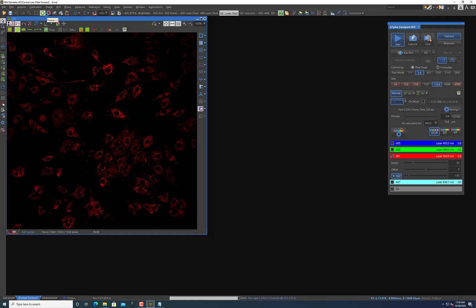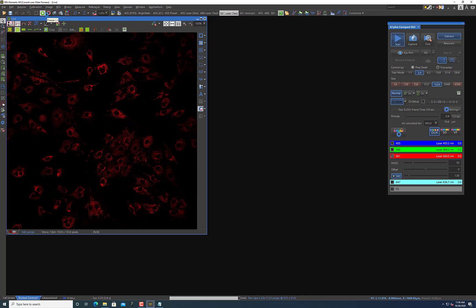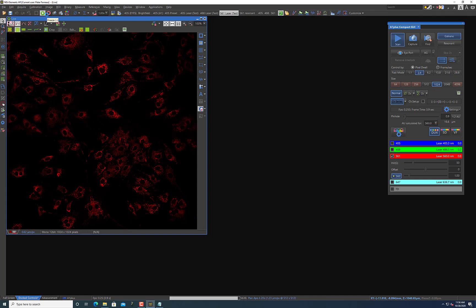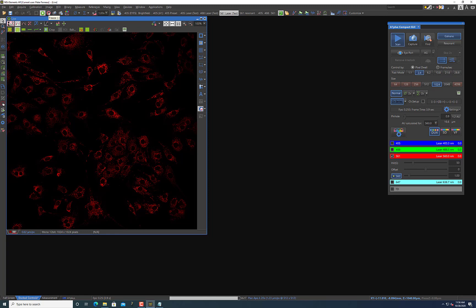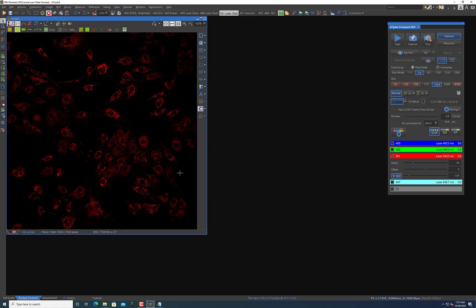The reason for this is because the galvano itself is just two mechanical mirrors that are aligned and placed in the optical pathway to scan laser light in either the X direction or the Y direction. In general, this is a slower, more sensitive approach, so you'll get really good-looking data, but it takes a while to scan the entire field of view that you're looking at.